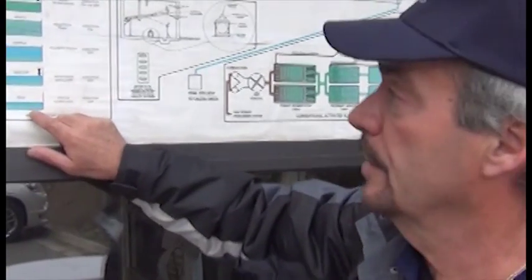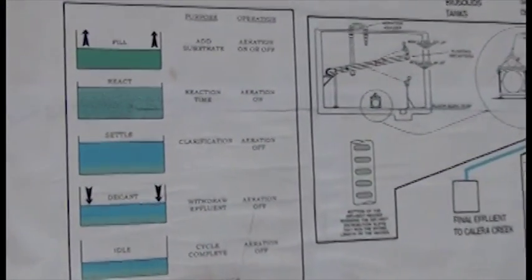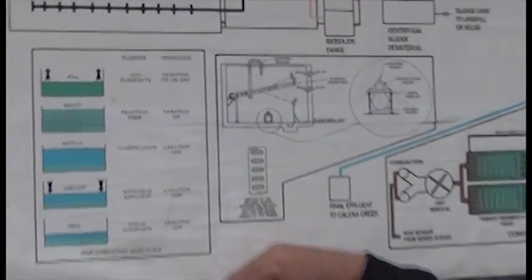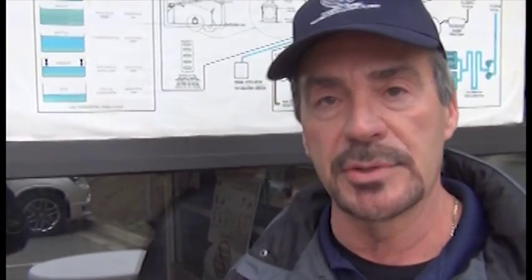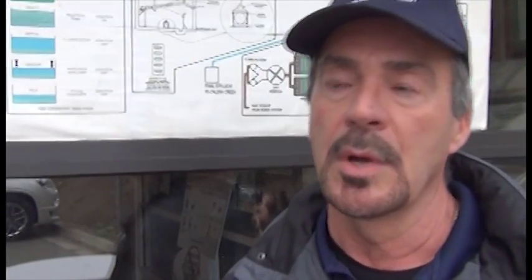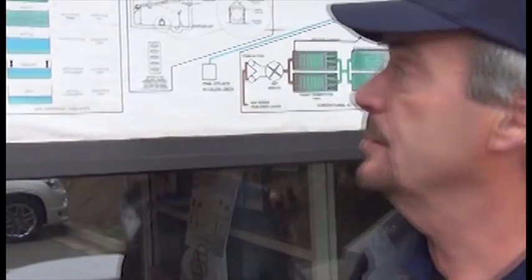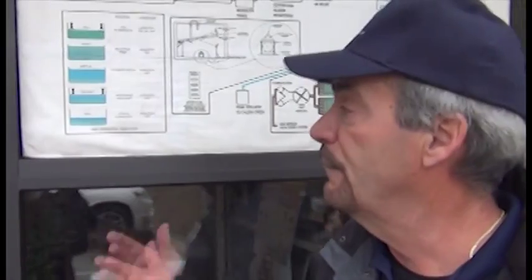The organisms are going to do the work. When the tank starts to fill, it fills five more feet, bringing it up to 20 feet. The computer senses that, shuts off the influent valve, and starts filling another SBR. Going back to the SBR we just filled — when it's full, it goes into react. A mixing pump comes on and a blower comes on. The mixing pump moves the organisms and material around the tank so they come in contact with each other. The blower pumps air into the water, producing dissolved oxygen — all healthy water has dissolved oxygen — so the organisms can breathe while metabolizing the food we just put in.